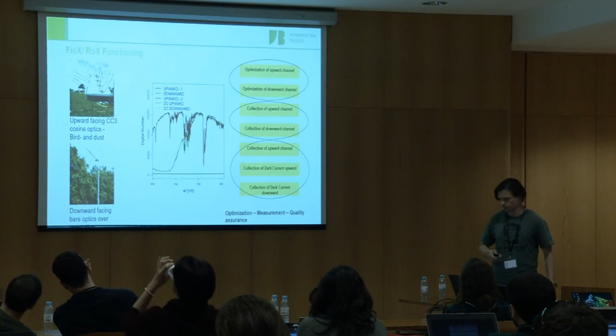The wavelength calibration also was introduced by Laura in great detail, so I just cover it roughly. We also use these gas emission lamps. For our case, we have argon and krypton available, and then you get an emission spectrum from these lamps that looks something like this in the real spectrometer, and you can derive the full width at half maximum from it, and also the spectral response curve, so to say, for the wavelength characterization, which is then the polynomial of third degree, which you also get with the calibration sheet for each instrument.